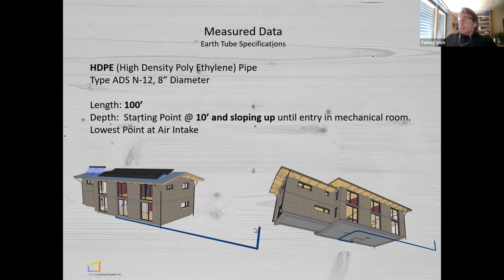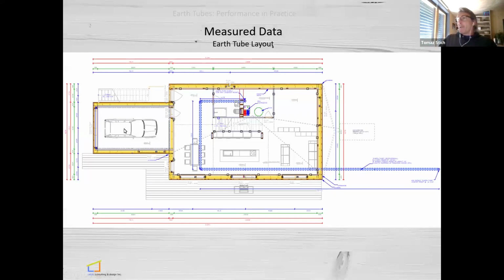So here, you will see some pictures right now. This is the air intake. This is a screenshot from my production model. This is the lowest point here. It goes straight down and then slopes up until it reaches here, the mechanical room. So we start at 10 feet depth and then slope up. It's a screenshot of the main floor. Here's the air intake on the right-hand side. It goes all the way, and then from here on, it's really warm under the slab.